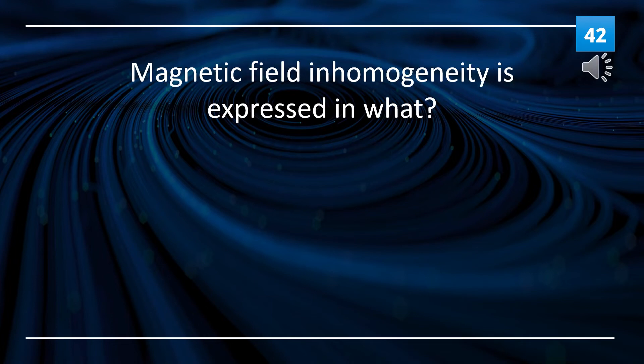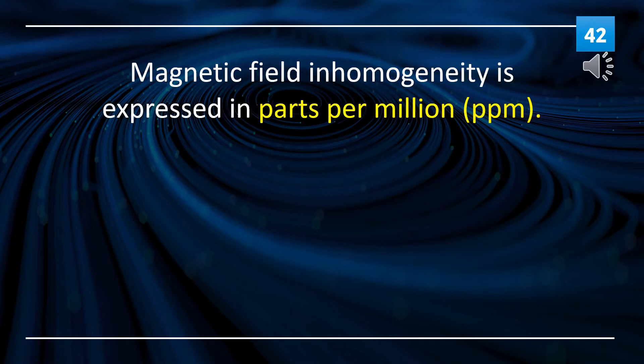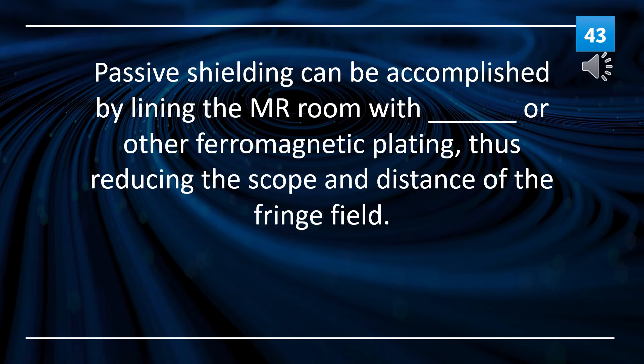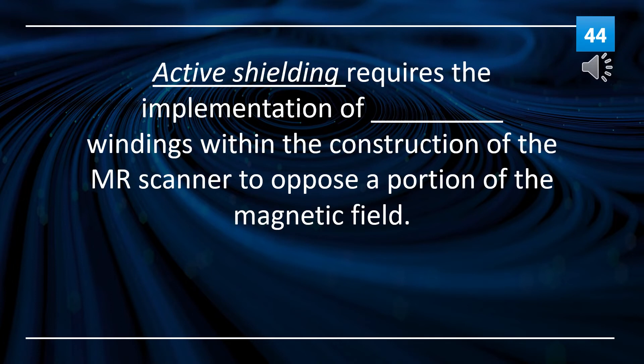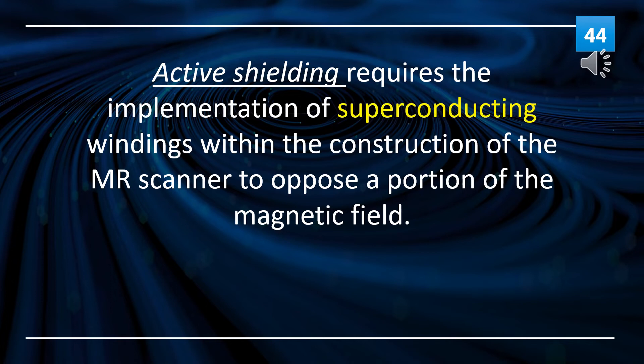Magnetic field homogeneity is expressed in parts per million (PPM). Passive shielding can be accomplished by lining the MR room with steel or other ferromagnetic plating, thus reducing the scope and distance of the fringe field. Active shielding requires the implementation of superconducting windings within the construction of the MR scanner to oppose a portion of the magnetic field.